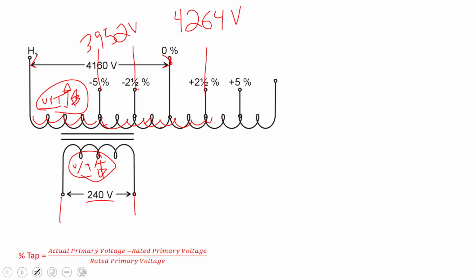So that's where this all comes from. We really got to think about the volts per turn ratio. When you see, oh, I'm on a negative tap, that means my voltage is low. I have to take turns out. If my voltage is too high, I have to add more winding into the transformer on the primary in order to get that correct volts per turn. Now, as you see here, I put the formula up here. It says percent tap. It's the actual primary voltage minus the rated primary voltage over the rated primary voltage. So that's the formula that's in your ILM.